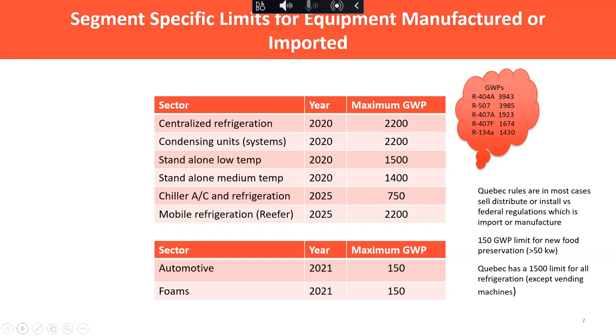One could say this is for new equipment, but to use the wording of Environment Canada, it's for equipment that's manufactured or imported. You can see on the right-hand side, GWP of 404A and 507 are 3,900. So as an example, in condensing units, you would no longer be able to use 404 or 507 in new condensing units.